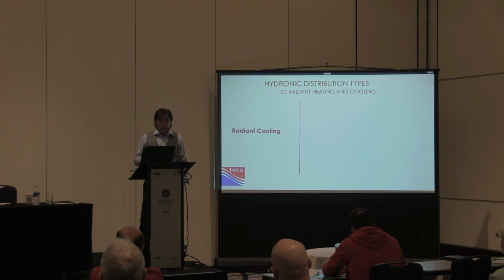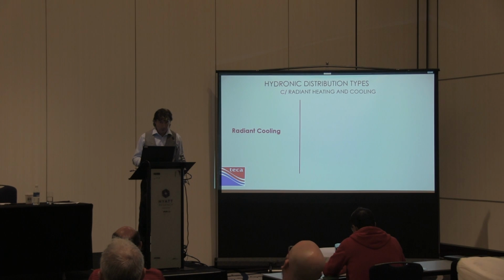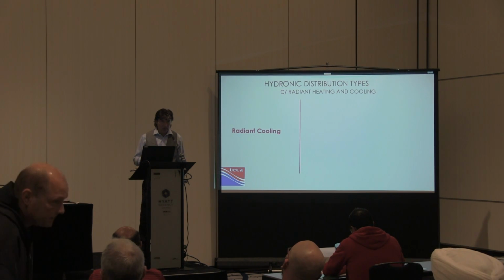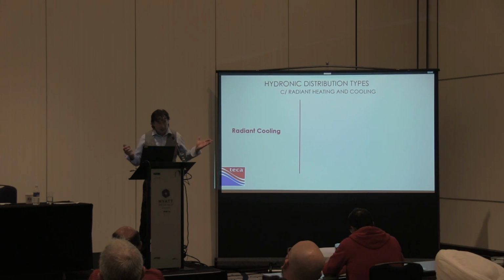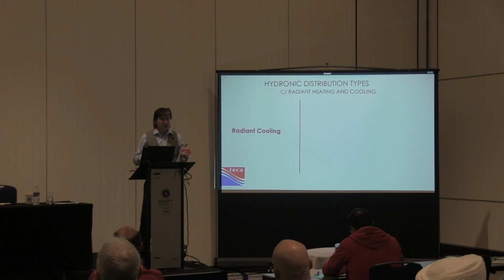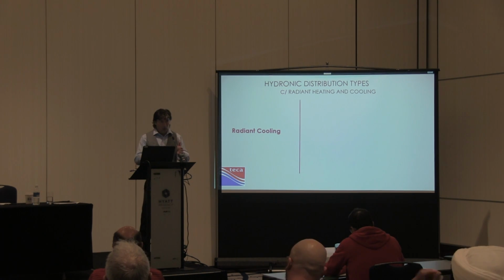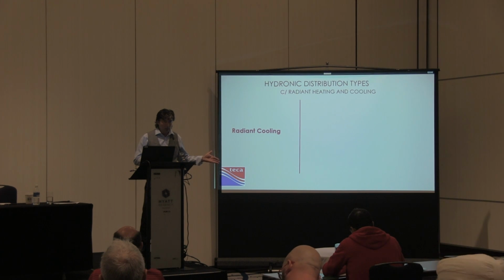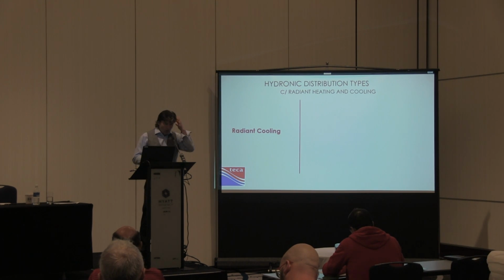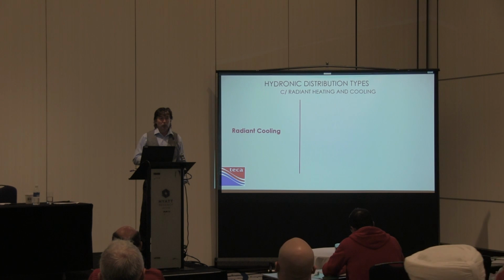And often, you'll find carpet in bedrooms, etc. So it's critical to analyze each room. If somebody's doing a radiant design for you and they haven't asked you what the flooring is, that's going to be a bit of a question in your mind right away. Okay, yeah, they start stapling down the second floor and maybe you don't even know what the flooring is. No, the homeowner hasn't made up their mind. That happens. But somebody's got to look at that, and our code says you take the worst case scenario. If you don't know, you better allow for the worst case scenario, which is like ugly carpet in there. Who knows, somebody puts that in later. So you have to factor these things in when you're doing the design. A lot of resistance in carpets, sometimes to the point where you cannot heat the room.